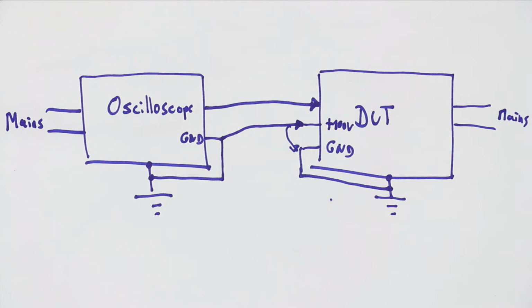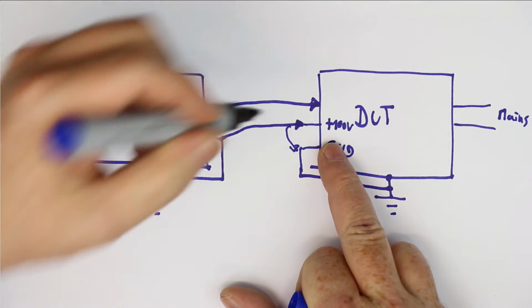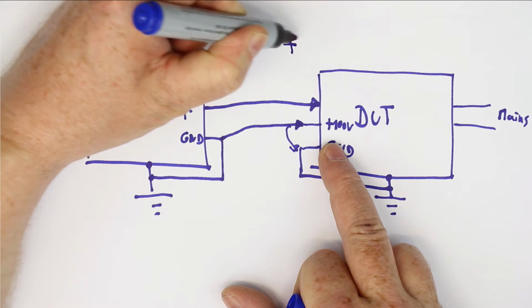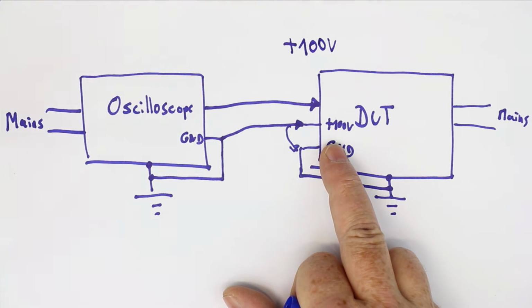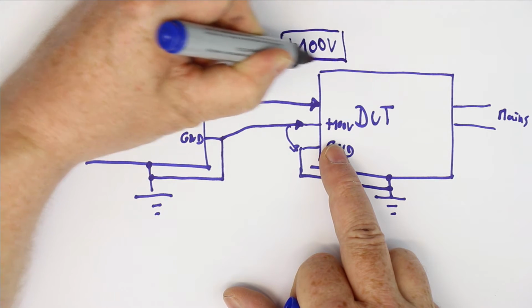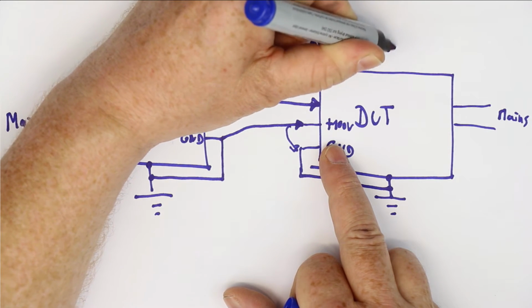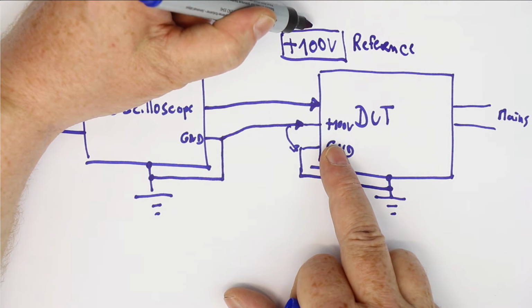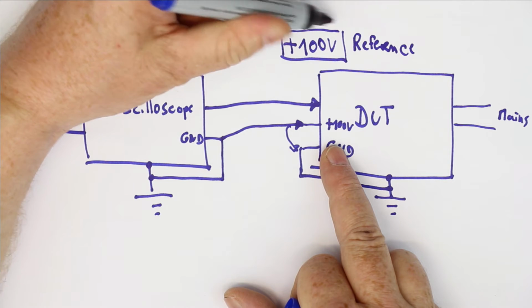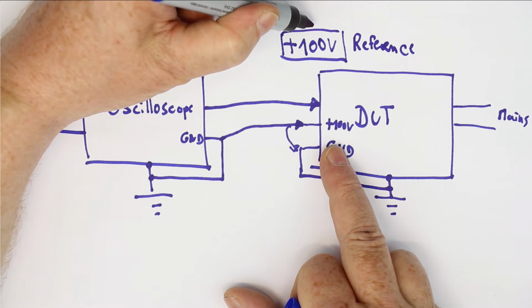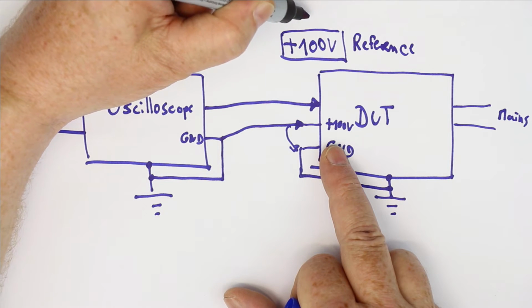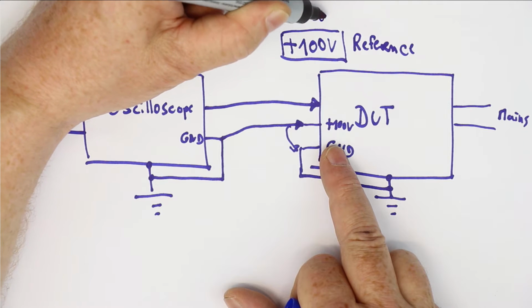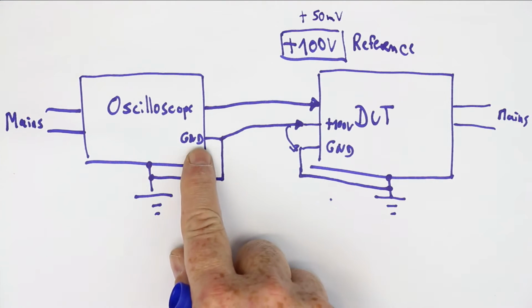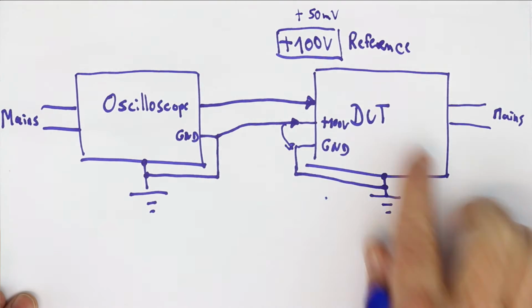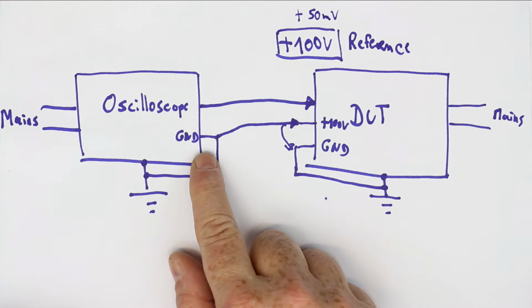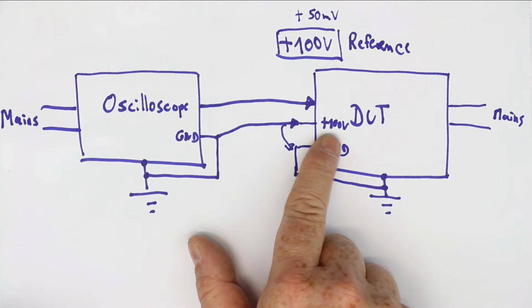This happens quite often. You have some voltage, let's say plus 100 volt, as your reference point, and you want to see if there's any AC voltage or other voltage superimposed on that 100 volt reference, say a few millivolts above. You cannot measure this relative to ground because the difference is simply too small.